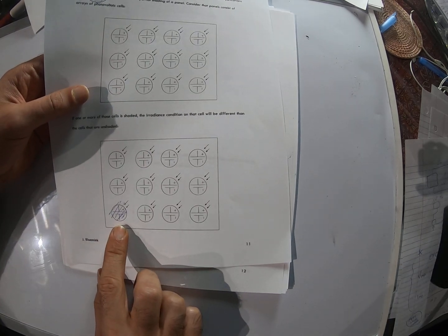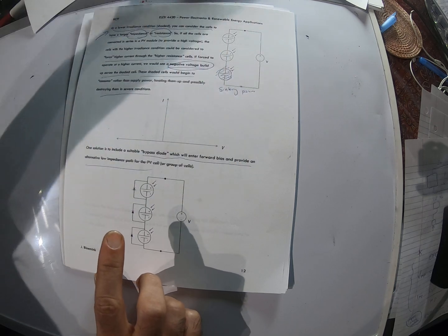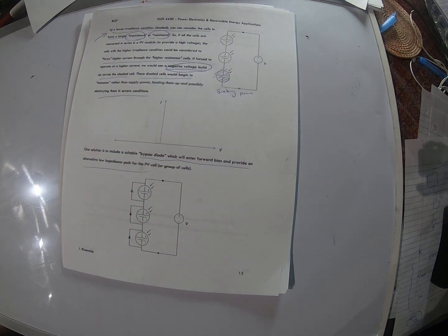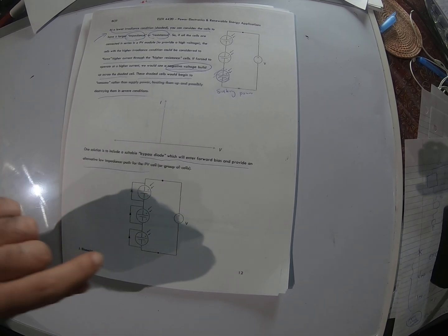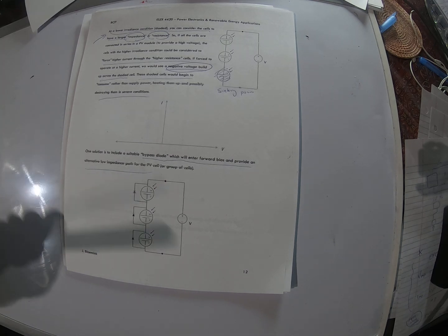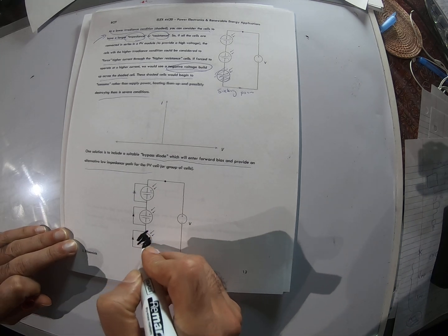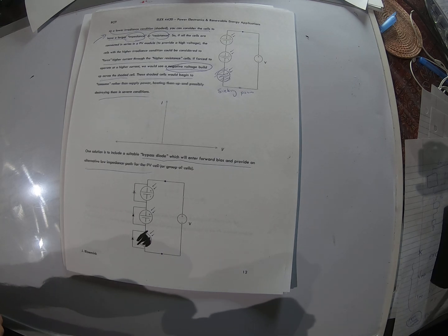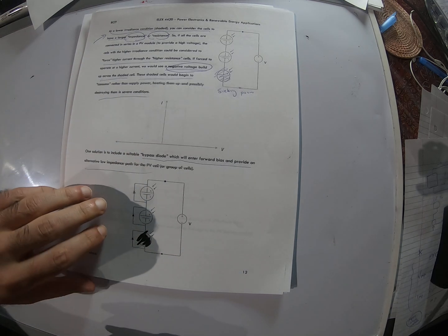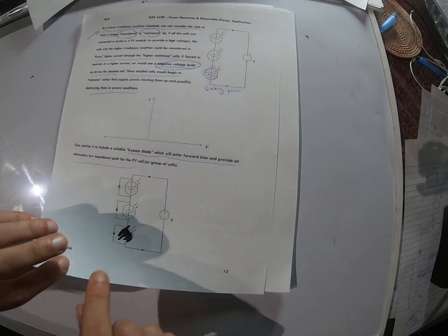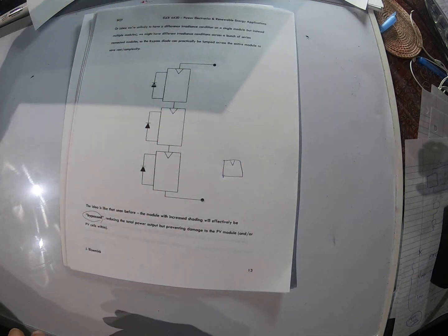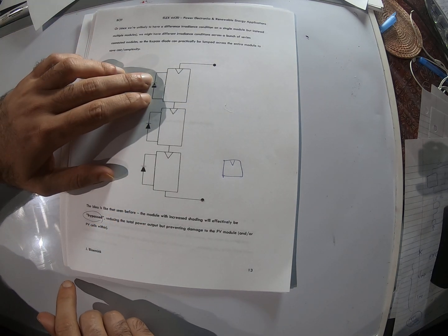So we covered perturb and observe, and we covered partial shading. If one of the solar cells is shaded, or if it goes out of order, that's why we have a bypass diode. We want to bypass that, because if one cell goes out of order, it would have high resistance and act like a sink. So it wouldn't be a source anymore, it would be a sink. That is what a bypass is for, and we would have the same thing for our panels.